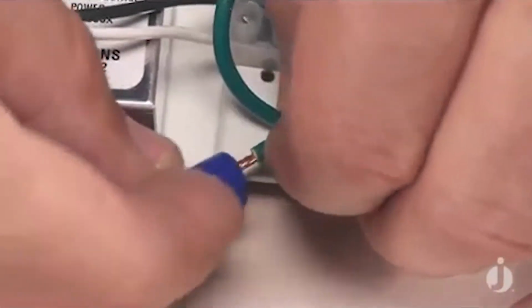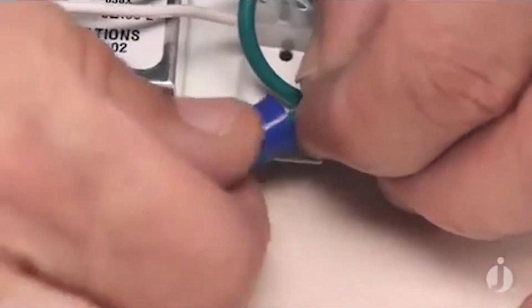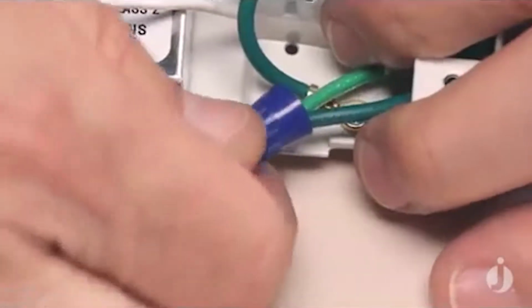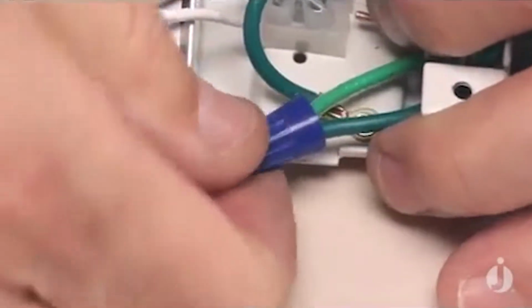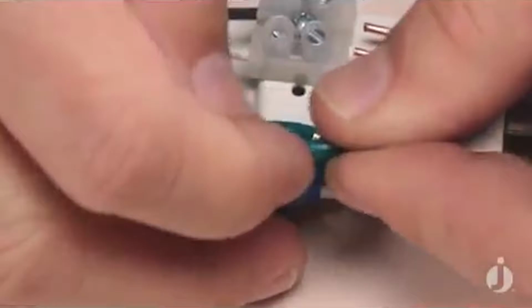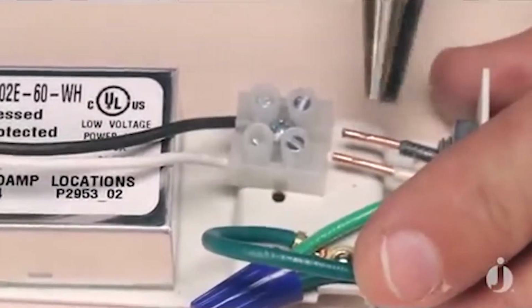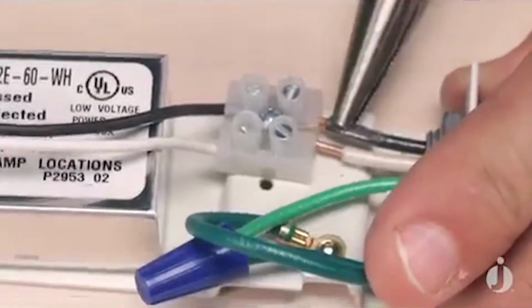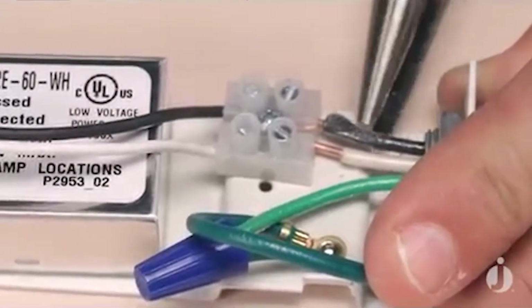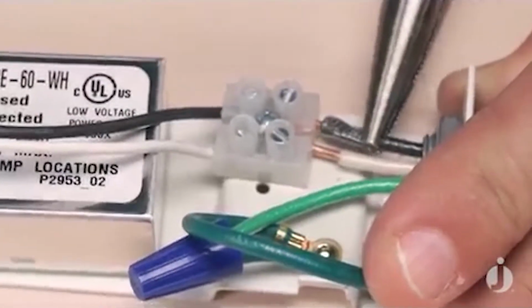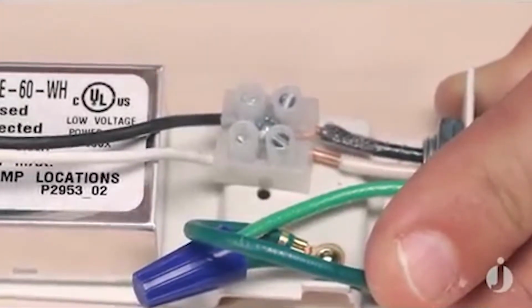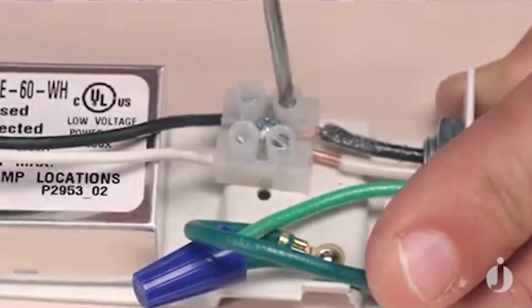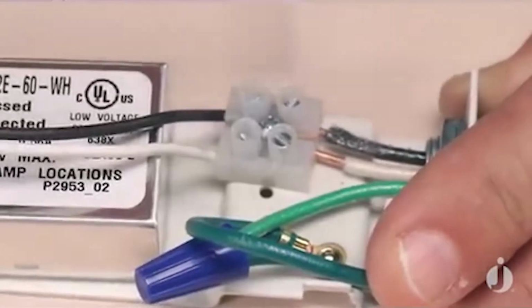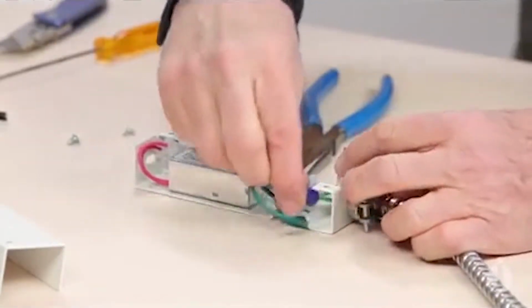In this case, my green ground terminal is loose inside of the housing. There's my ground connection. And my black connection, this of course is a little terminal block, is going to go into the corresponding black lug. And let's tighten that down. Next, the white.